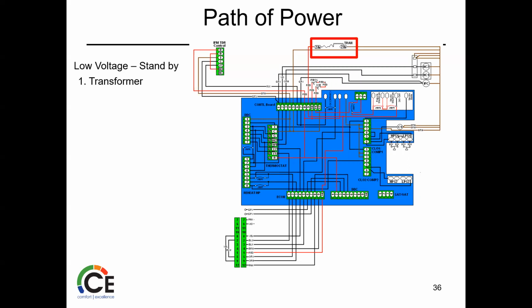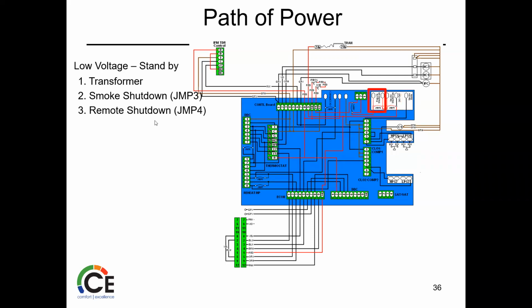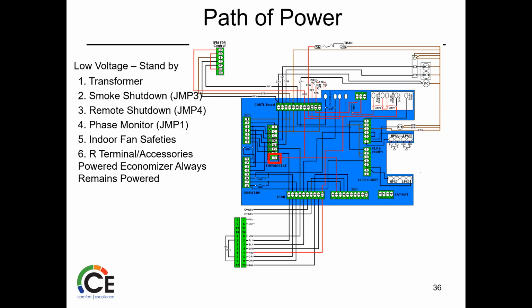So the transformer obviously comes in and hits terminal 9 there, and then it's distributed. So again, first thing, 9 comes in. It's going to run through 10, come back 11, go through occupancy. It's going to jump that phase monitor thing there where it says jump 1. And then it's going to start to go through remote shutdown, smoke shutdown. So it runs through that whole path first, hits that, hits here, there, and then finally at your thermostat.